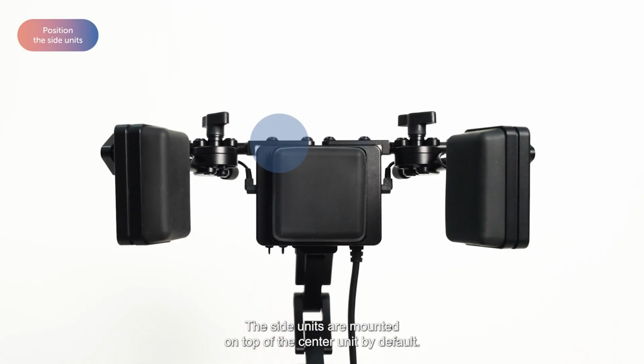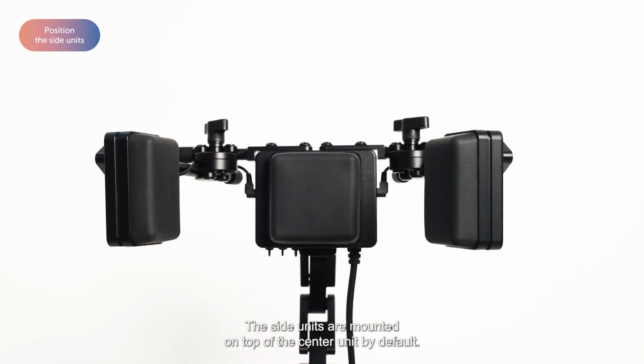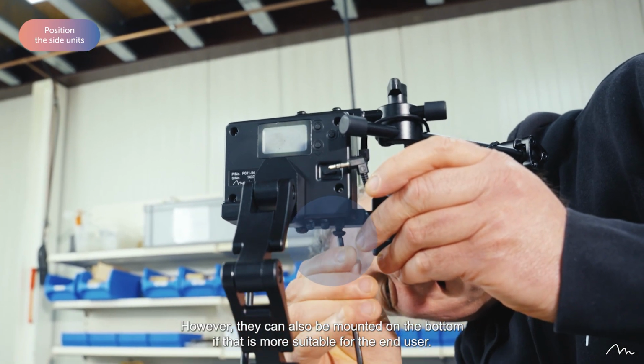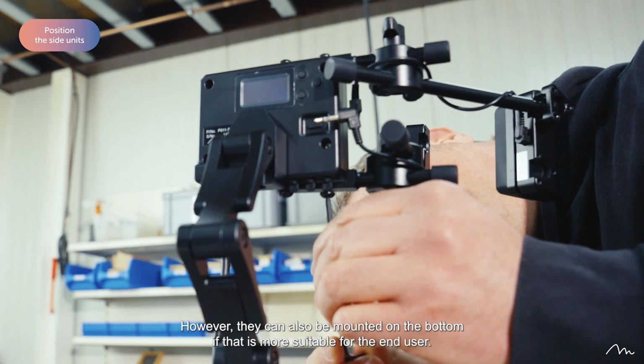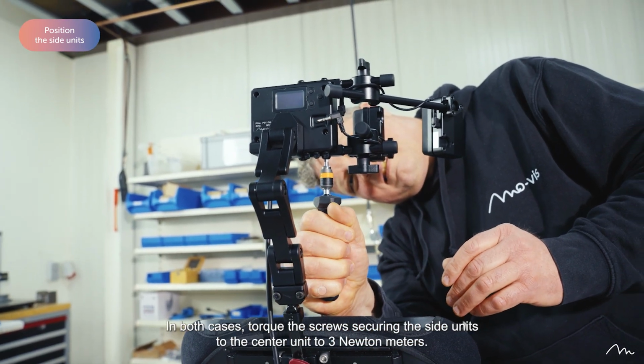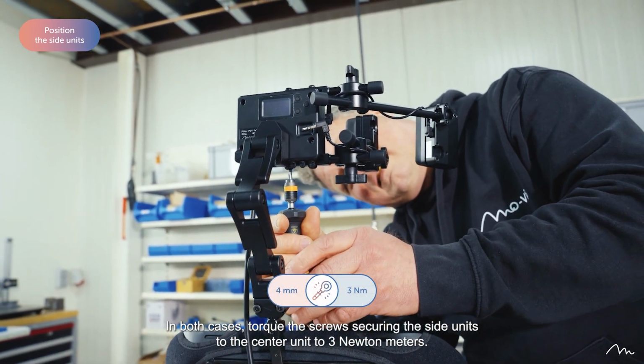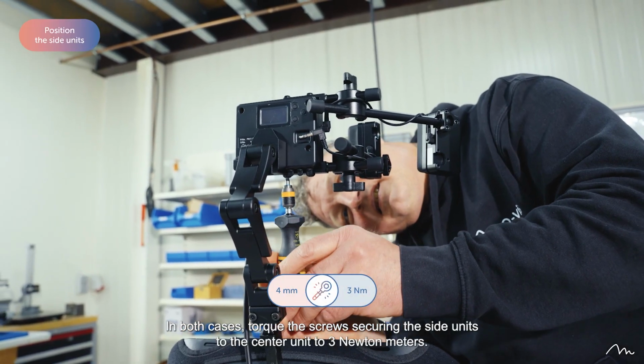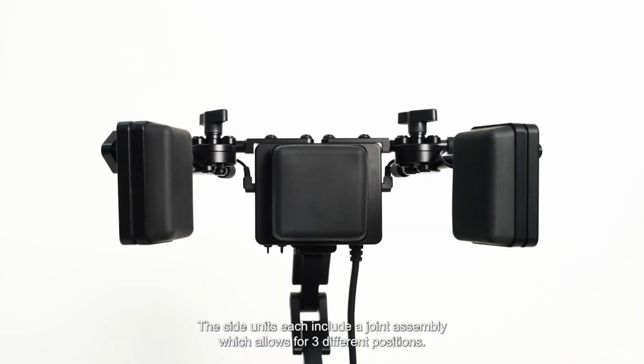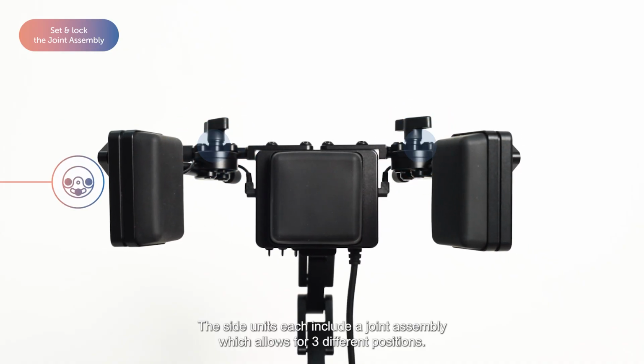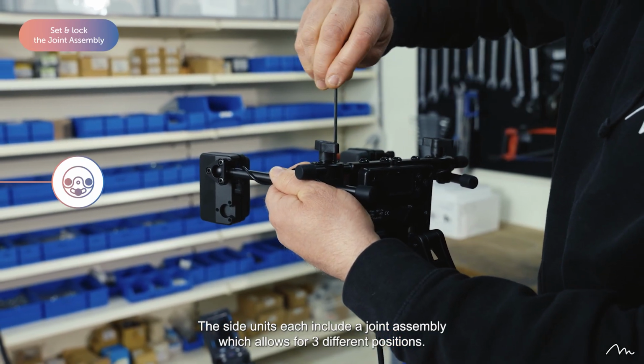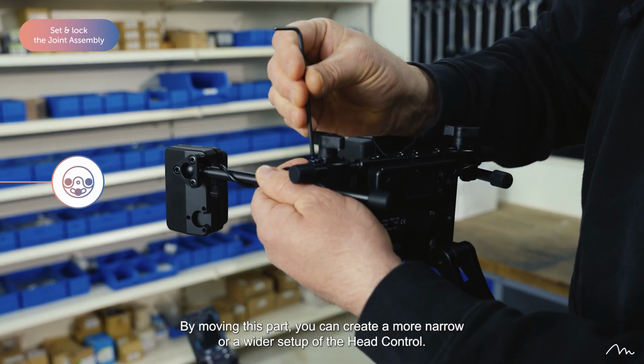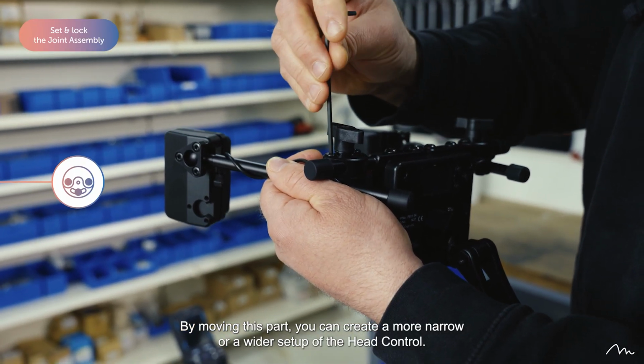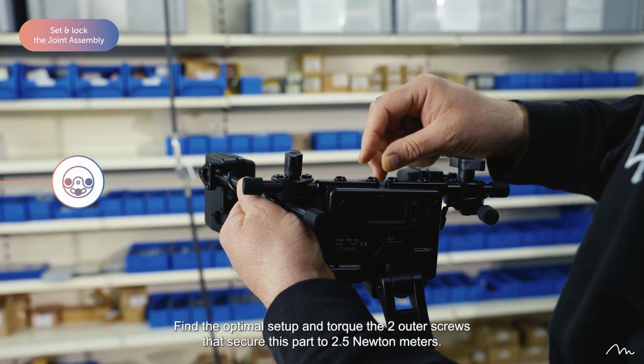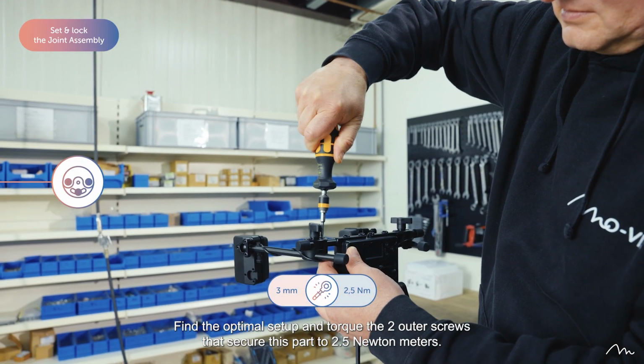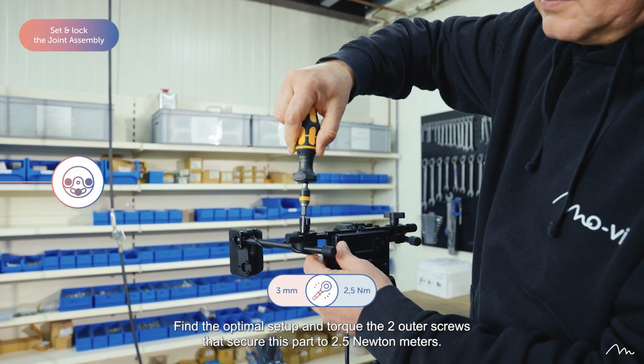The side units are mounted on top of the center unit by default. However, they can also be mounted on the bottom if that is more suitable for the end user. In both cases, torque the screws, securing the side units to the center unit to 3 Newton meters. The side units each include a joint assembly, which allows for 3 different positions. By moving this part, you can create a more narrow or a wider setup of the head control. Find the optimal setup and torque the 2 outer screws that secure this part to 2.5 Newton meters.